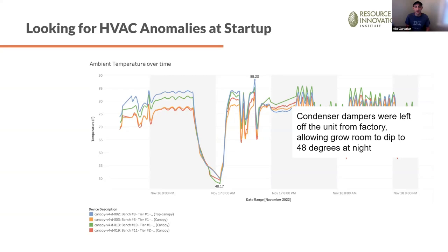These condensers had fans on them, and a piece was left off at the factory that kept the heat in them at night. In this case, with plants in the room, the temperature went from 85 to 48 degrees in a cannabis grow room, which is bad. These are the things you have to watch out for and plan for ahead of time. We caught it on the first night it happened and identified it quickly, but still, it would have been better if plants were not in the room yet. Next slide.